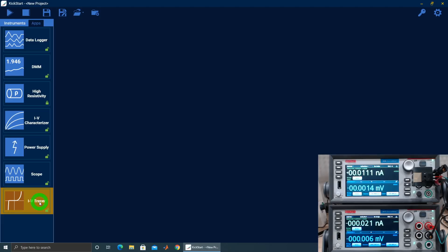If I go under the Instruments tab, you can see that the 2450 and the 2470 are both recognized. So both of them are simultaneously connected to the PC using 2 separate USB ports. At the same time, you can connect the TSP interface to the back together in order to allow for really high-speed triggering. So you can't daisy chain them like you can do with this scripting using the Kickstart. You have to simultaneously connect it to the PC.